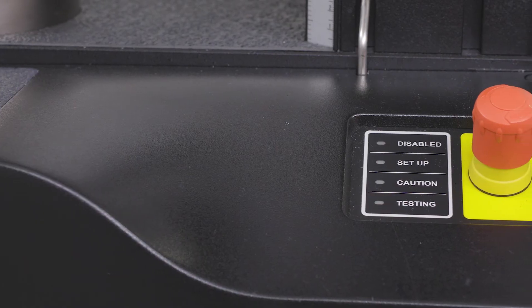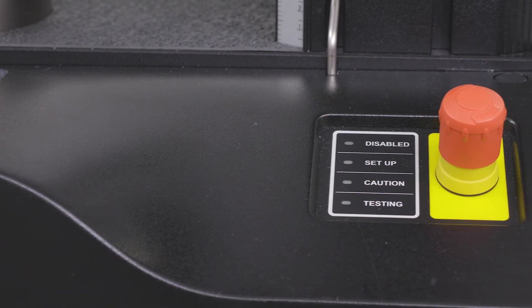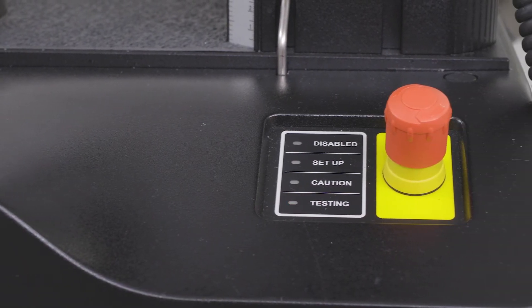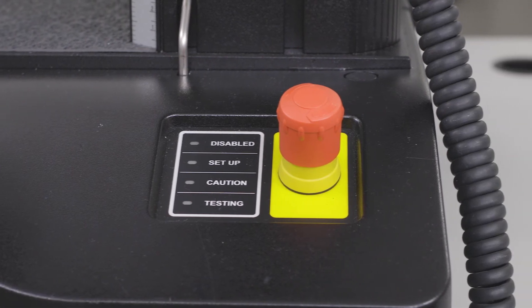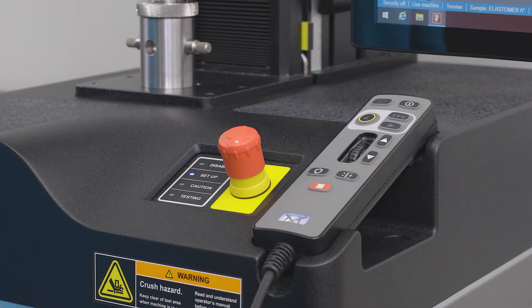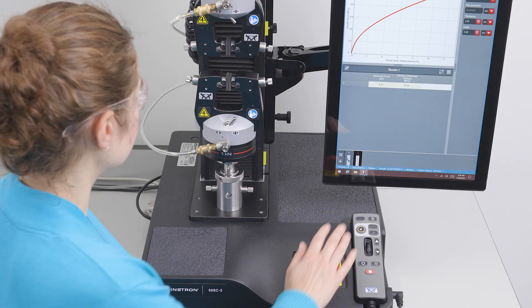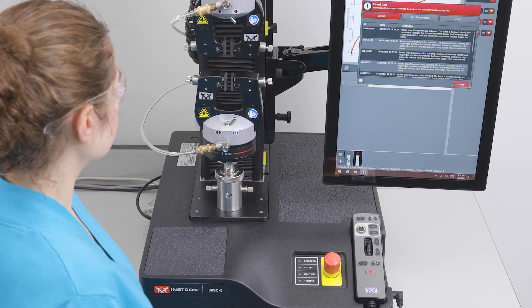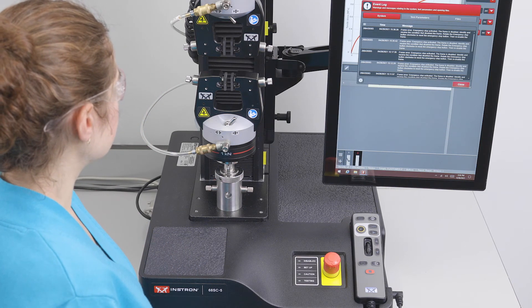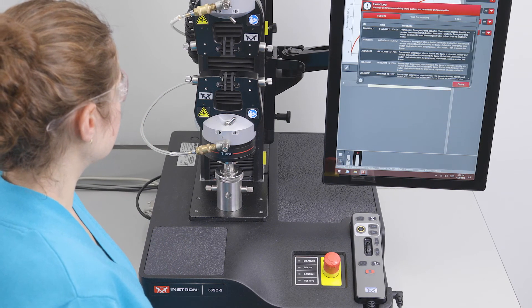The air kit is tied into the operator-protect circuit, meaning that the grips will open any time the frame is disabled by the emergency stop. When the machine is in disabled mode, the crosshead cannot move and the grips cannot be closed.